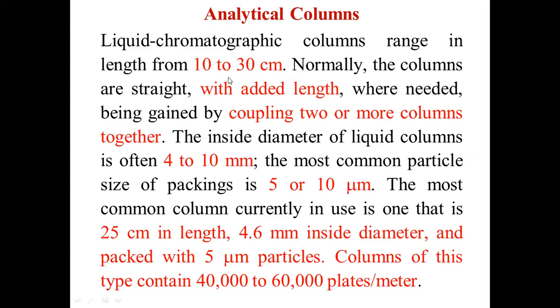So this will have a length from 10 to 30 centimeter. Even we can combine 2 or 3 columns in order to increase the column efficiency. So a minimum of 10 centimeter to 30 centimeter column we can use. These columns are straight. Of course, we can add length by coupling 2 or more columns. The internal diameter will be from 4 to 10 millimeter, and the packing material, meaning the stationary phase, will have a particle size from 5 to 10 micrometer. The most commonly used column has the dimension of 25 by 4.6 millimeter by 5 micrometer. Why do we say these 5 micrometer particles?